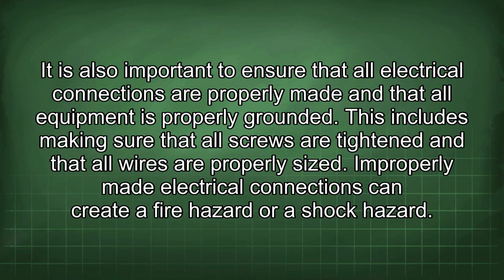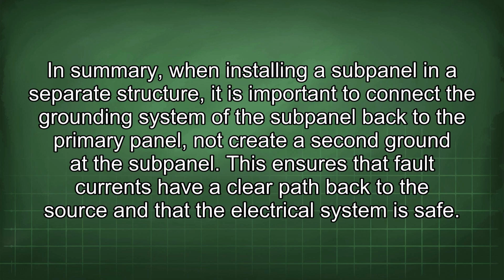It is also important to ensure that all electrical connections are properly made and that all equipment is properly grounded. This includes making sure that all screws are tightened and that all wires are properly sized. Improperly made electrical connections can create a fire hazard or a shock hazard. In summary, when installing a subpanel in a separate structure, it is important to connect the grounding system of the subpanel back to the primary panel, not create a second ground at the subpanel. This ensures the fault currents have a clear path back to the source and that the electrical system is safe.